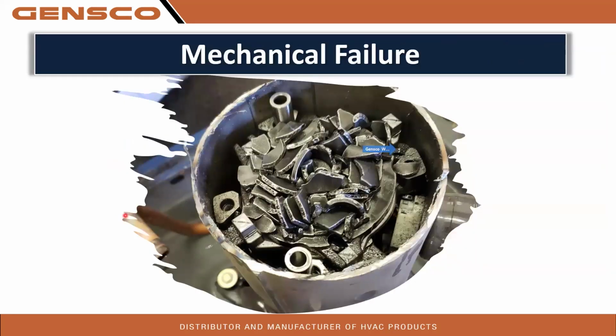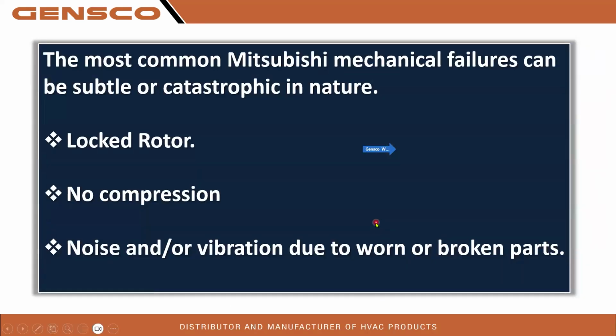We'll start off talking about mechanical failures. As you see in this picture, that was pretty catastrophic failure. The most common mechanical failures can be subtle in nature, such as no compression, or they can be catastrophic, locked rotor, noise or vibration. There may be, and that would be subtle, a little bit of vibration because it's out of balance due to wear. Probably the most common one you're going to run into is the locked rotor when in a mechanical failure.